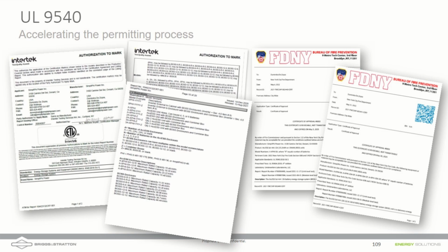All of this goes into a report. So if you're looking at battery storage products, make sure it has UL 9540 and has gone through UL 9540A testing. Because of our safety, our batteries are one of the only ones that can be installed in residences in New York City. If you've seen the news, they're very concerned about battery storage because of issues with e-scooters.